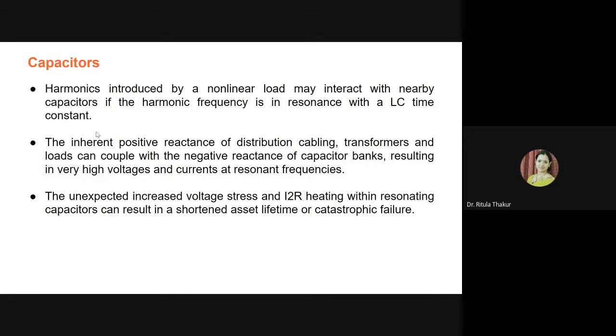to error. Apart from that, the inherent positive reactance of distribution cabling, transformers and loads can couple with the negative reactance of capacitor banks, resulting in very high voltages and currents at resonant frequencies. Then unexpected increased voltage stress and I-square-R heating within resonating capacitors can result in shortened asset lifetime or catastrophic failure.